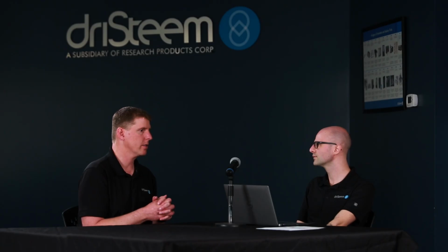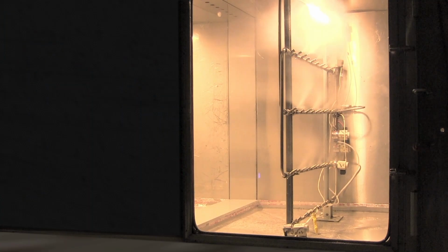And then maybe you want to end the wet section, because you don't want to have it forever in an air handler. Because an adiabatic type process doesn't happen as fast as steam. You're talking feet before that gets absorbed. And the more time that the water droplets have with the air, the more of it will be absorbed. You don't want to send it down the drain if you can avoid it. Right. And so having that time, and then maybe you want to end it and have a mist eliminator at the end to make sure that you're not carrying any of that mist downstream onto your fans or other pieces of equipment. So you're constraining what that is. You're planning for, okay, it's wet. So typically stainless steel, and you've got drain pans.